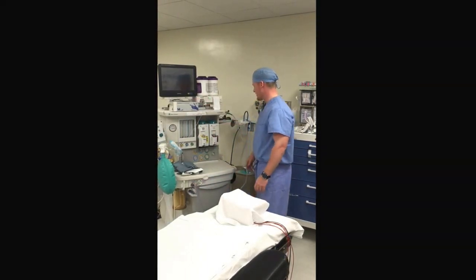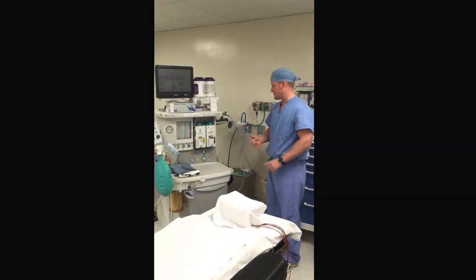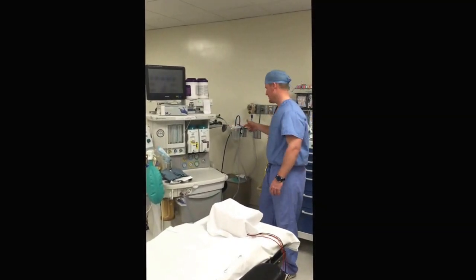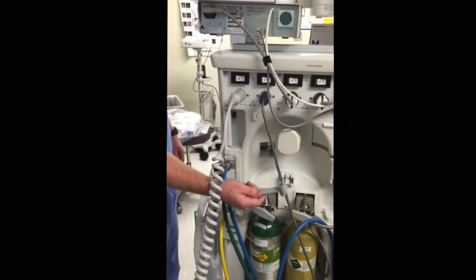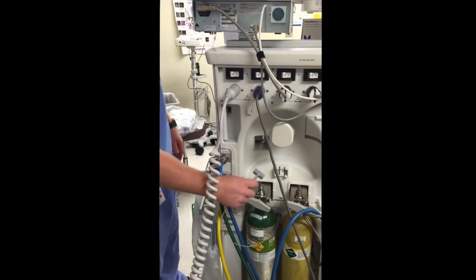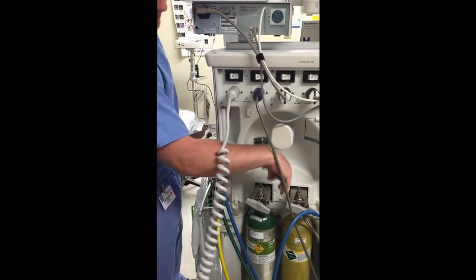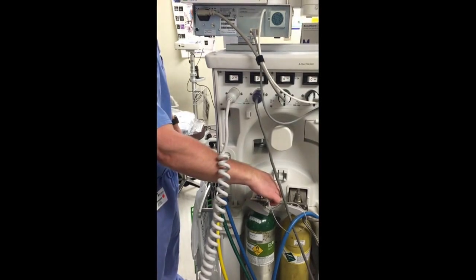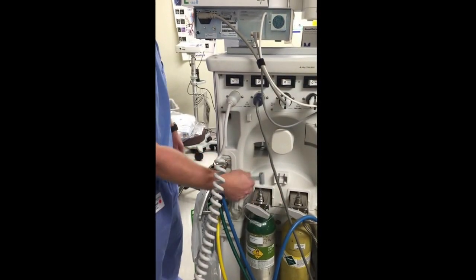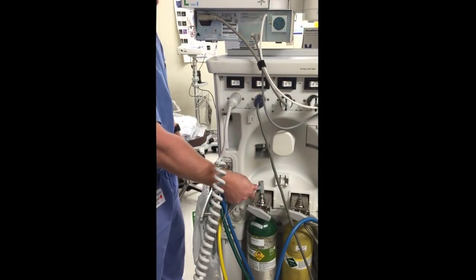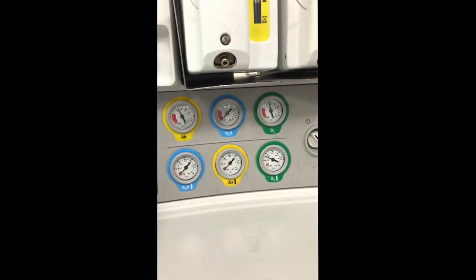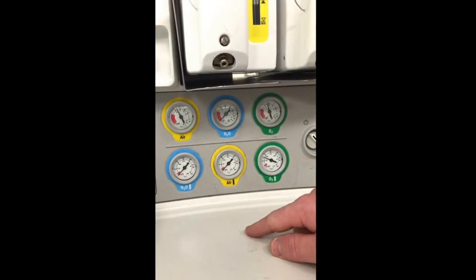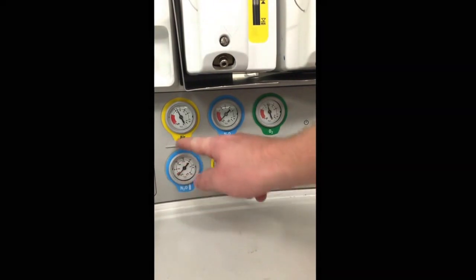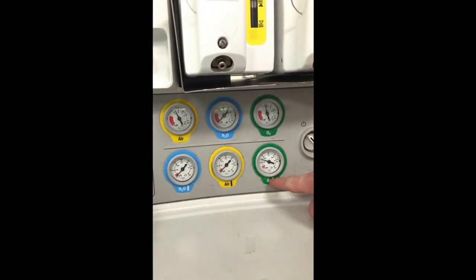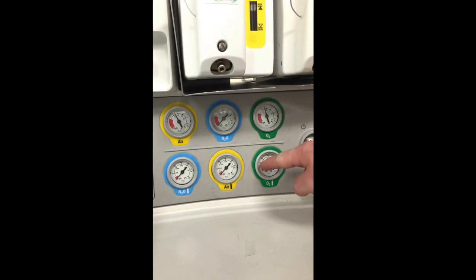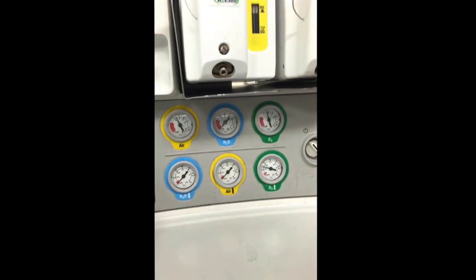And then the next part you'll check is your high pressure system, which includes your cylinders on the back of the machine. The wrench has two sides to help you turn and open the valve, open the cylinder. And after you've opened it and the pressure's gone in the system, you can close it. On the front of the machine, you can see your pressures for the cylinders and your pipeline pressures. So this is our oxygen cylinder, which is adequate in case we would lose our pipeline pressure.